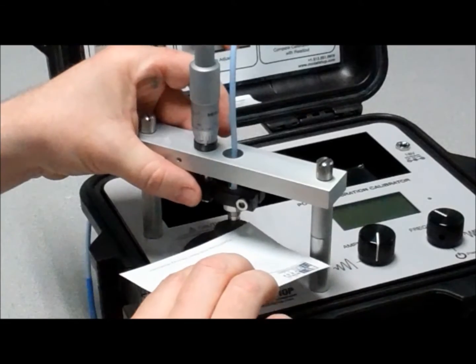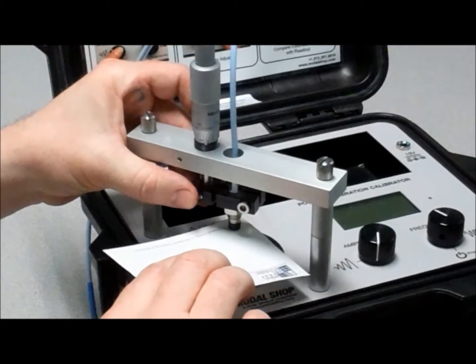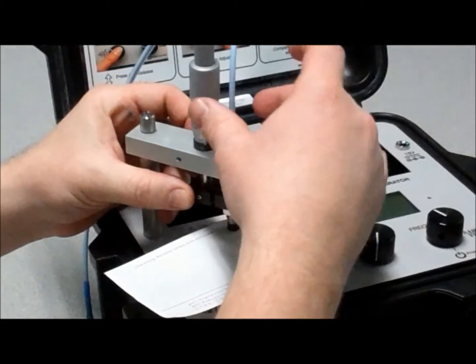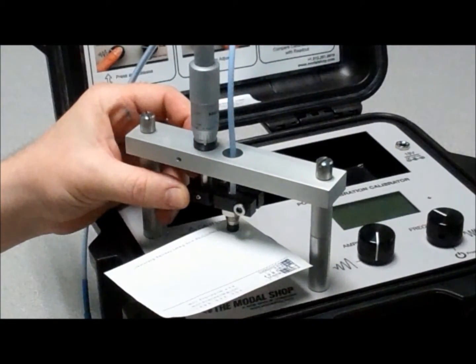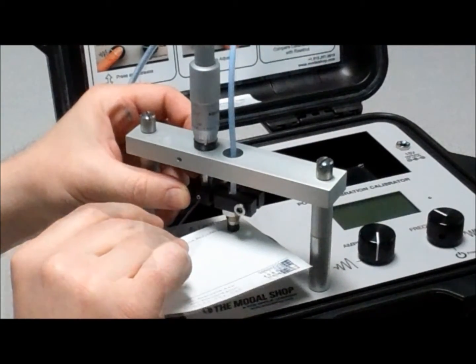In order to get the gap set at approximately 3 mils, place a standard piece of paper between the probe and target. Lower the probe until you feel drag on the paper.